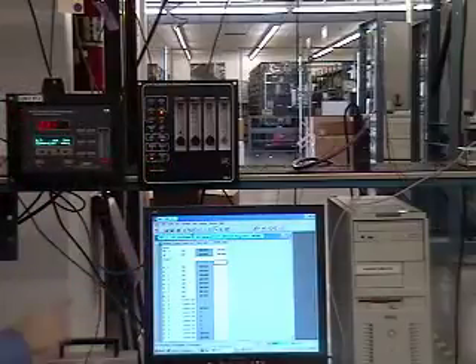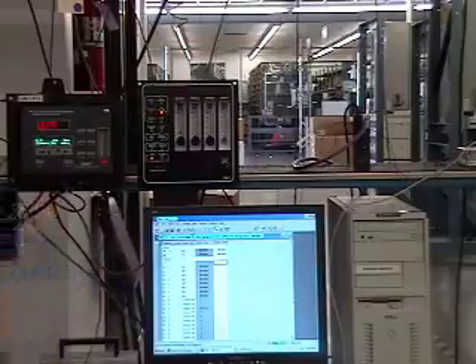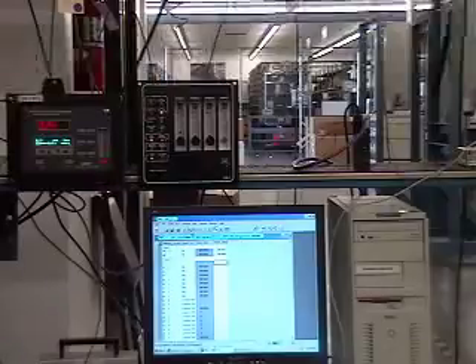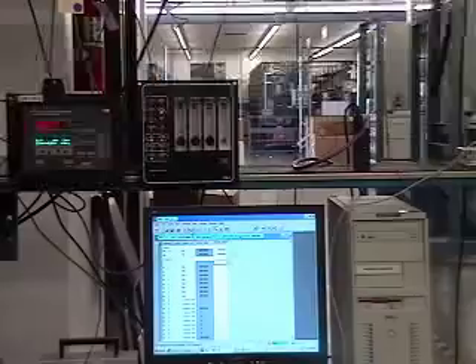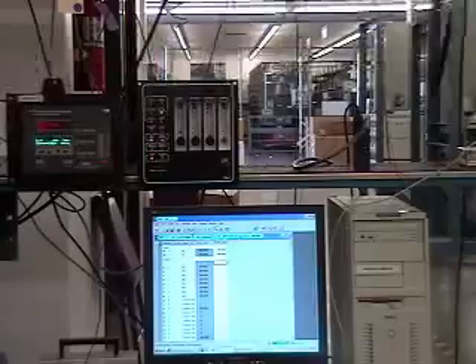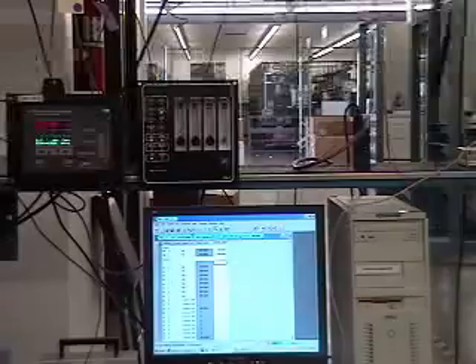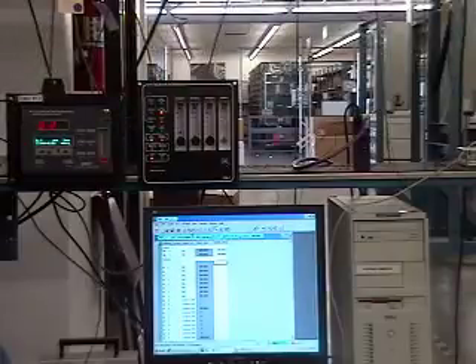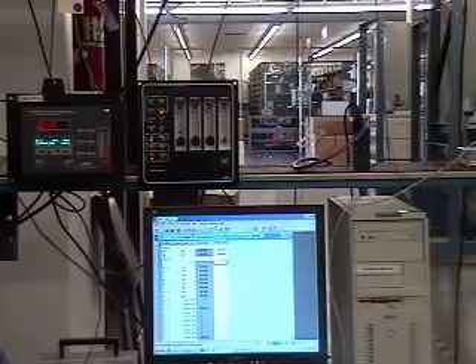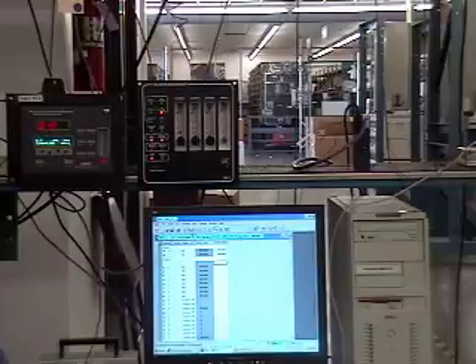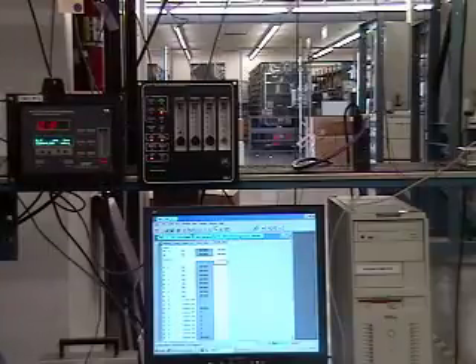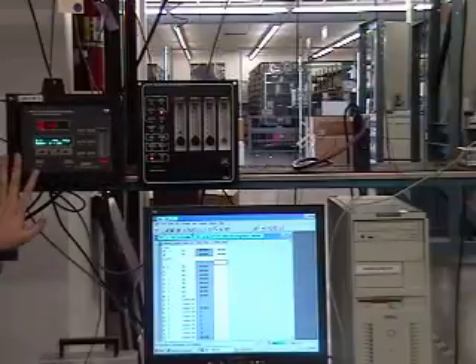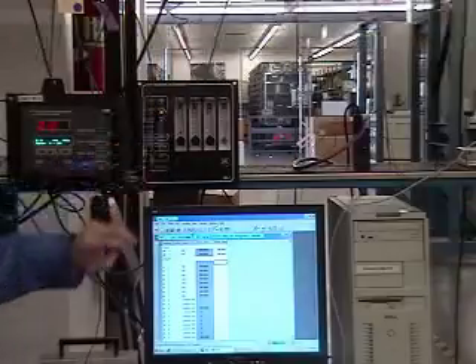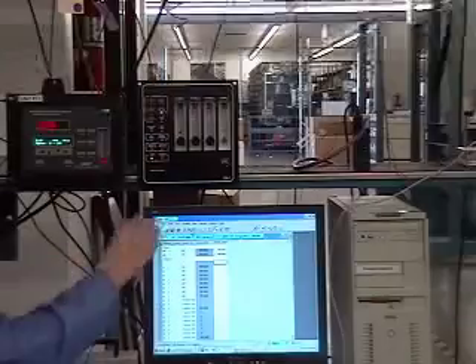Open up the low cal valve. The analyzer goes to 0 because the BB1 told the analyzer, hey, you need to go to 0. And we wait for the 0 to be done. Alright, the analyzer finished zeroing. You return back to analyze mode. So you can see that the valve is still open until I remove the command. Tell it to be in 0 mode, 0 valve. So I'm gonna close it.